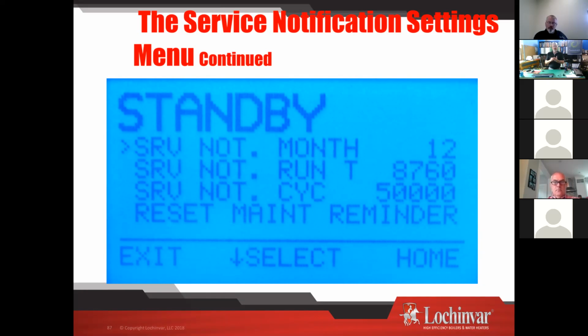So then it used its proximity detector of where's your van. And as soon as your van backed out of the driveway, it would trigger service notification, which was outstanding because the homeowner came home. They're all excited. They go down and say, why does my boiler need to be serviced? So we now have you set that runtime in there when you set the date, just so it wasn't giving you that little premature thing. Because everybody really liked that service call. Hey, I just got home and my boiler says service due.